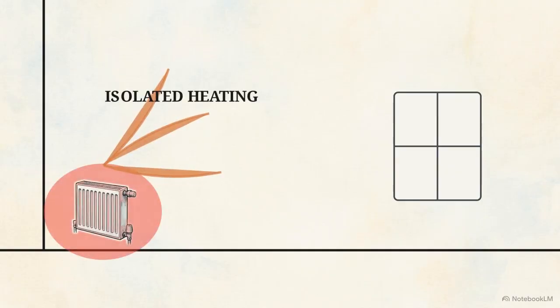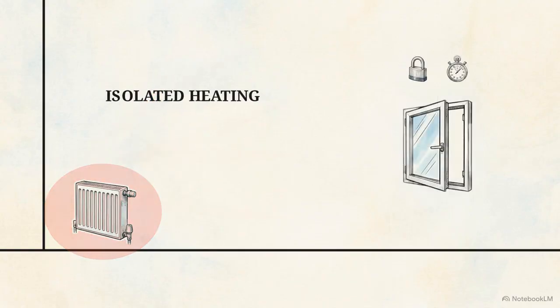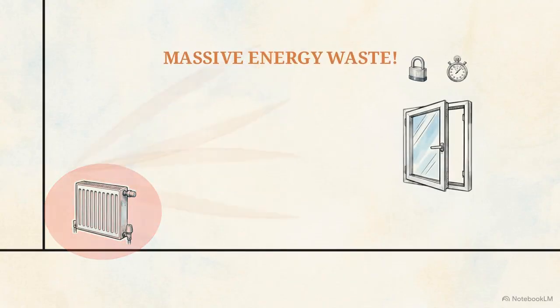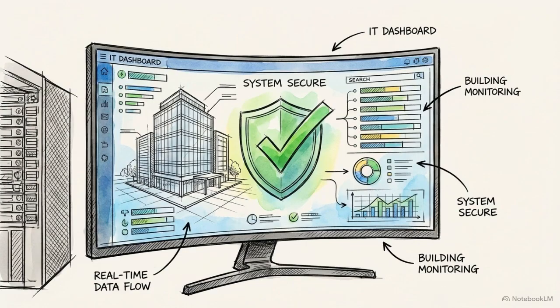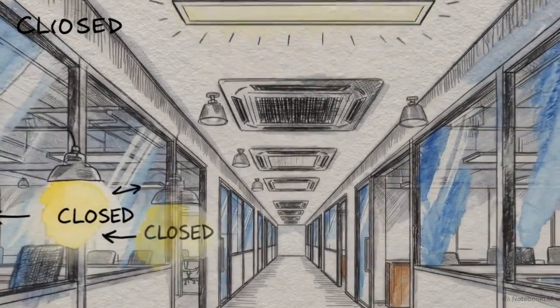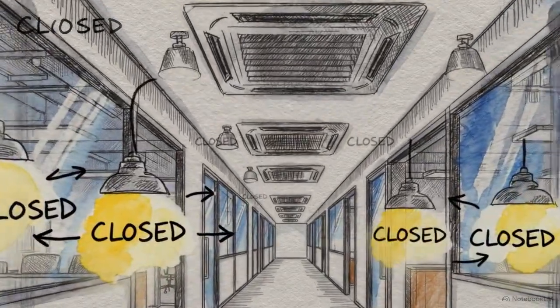Left isolated, these systems waste tremendous energy. A heating system might run at maximum capacity trying to warm a room, completely unaware that the security system just opened the ventilation windows on a timed purge. By bringing all of these physical systems onto a single IT dashboard, facilities teams can establish rules to detect and resolve these physical conflicts. The true value of a smart building lies in cross-system behavior. A change in one domain instantly triggers a coordinated response across the facility.